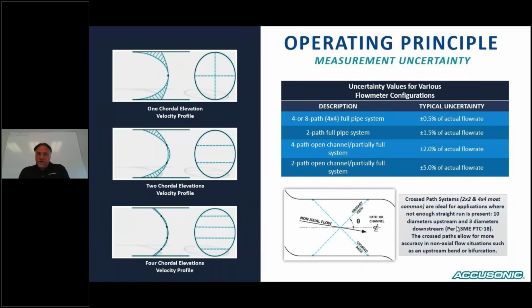Getting into the measurement uncertainty slightly, these are our typical uncertainties that we expect for various configurations. The detail on the left here shows what the integration uncertainty looks like. So kind of along the lines of any type of measurement, the more times you measure something, the more accurate you're going to be. So you can see on the left-hand side here, if you are only measuring a single point and trying to resolve the average velocity from that, you have a much greater uncertainty than down at the bottom here where you have 4 chordal elevations. You can see that uncertainty band gets much tighter because we're actually measuring those at 4 discrete points.